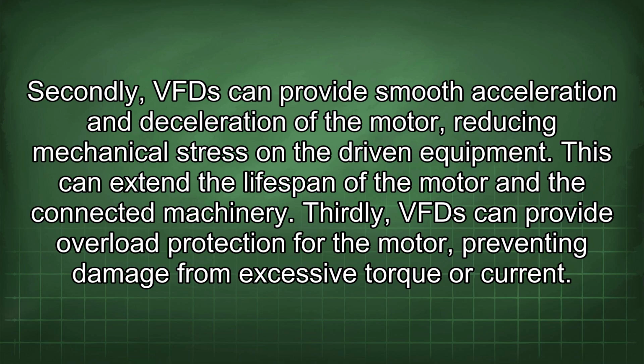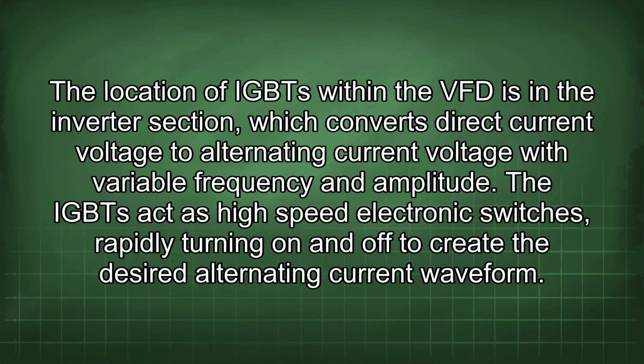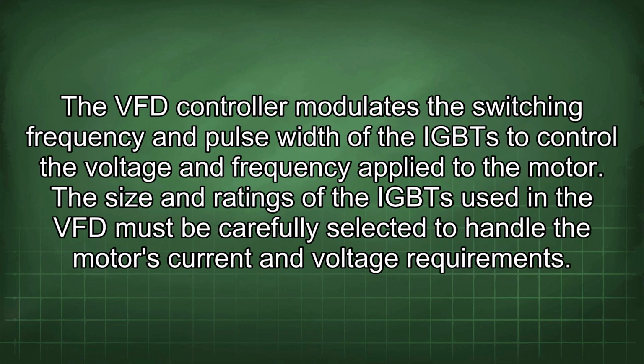Thirdly, VFDs can provide overload protection for the motor, preventing damage from excessive torque or current. The location of IGBTs within the VFD is in the inverter section, which converts direct current voltage to alternating current voltage with variable frequency and amplitude. The IGBTs act as high-speed electronic switches, rapidly turning on and off to create the desired alternating current waveform.